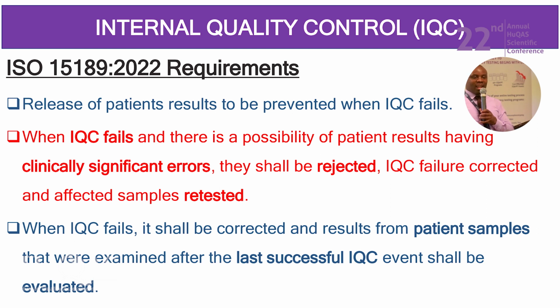And therefore, we advise, to avoid this kind of costs, make sure your machine is working properly by running the IQCs and then subject it to patient samples. Because if you happen to run them together with the patient samples and then the IQC fails, you'll have to go back and do what? And retest the affected samples, just to confirm that they were not affected by the same problem that affected IQC samples.